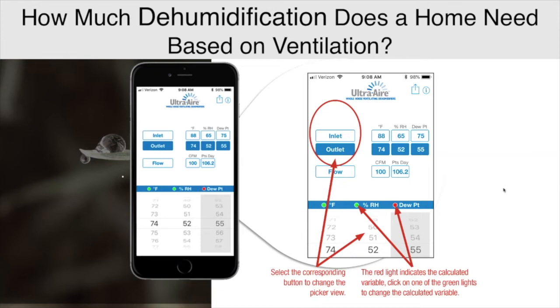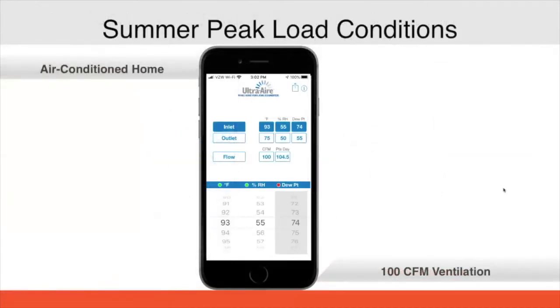So we're going to break that down into a couple different scenarios here. Summer peak load conditions, I've got 93 degrees, 74-degree dew point. The outlet in my house is 75/50, which really should be our ACCA design or Manual J design conditions right there. And I have 100 CFM, so I'm going to need 104 pints of water removal a day. Now, running at that peak load, my AC system is probably doing an okay job of keeping up with that moisture load if it's running at peak conditions for a large part of the day.